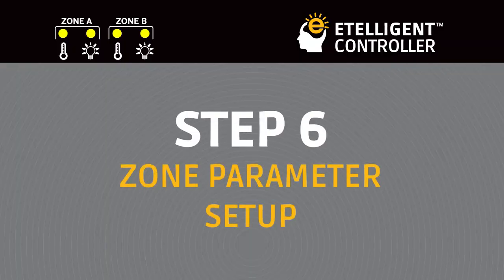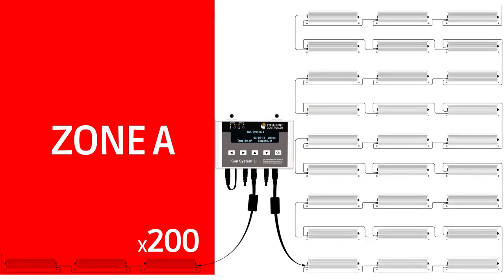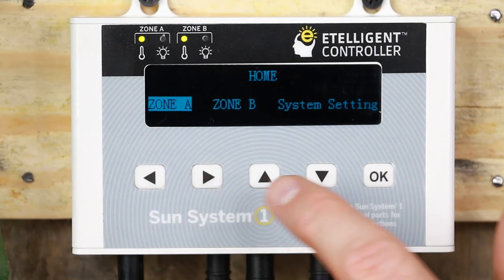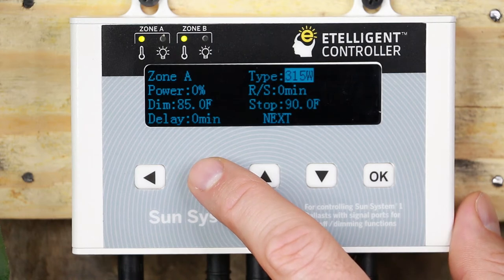Zone Parameter Setup. The Sun System 1 Etelligent Controller can control up to 400 ballasts split up evenly into two zones, 200 ballasts each. Each zone can be controlled independently based on the settings entered. Press OK to enter into the home screen. Use the arrow keys to select the zone you wish to modify and press OK. On the screen, you can change these parameters for the current zone: Type, which is the ballast wattage setting.